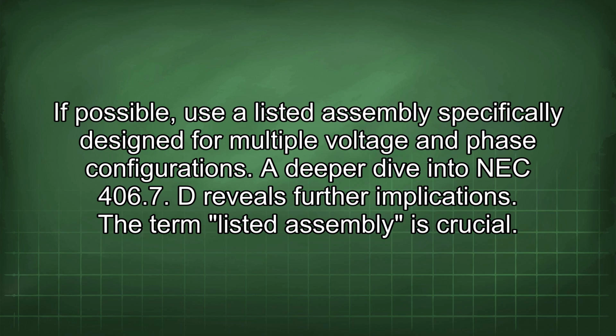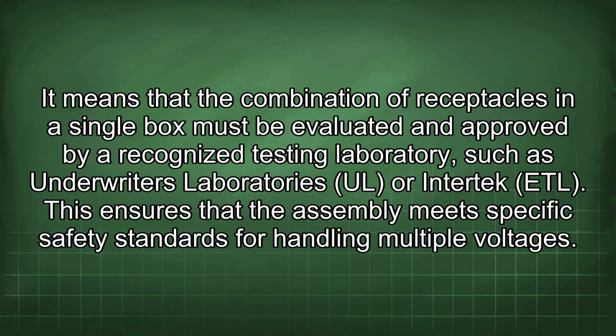A deeper dive into NEC 406.7(D) reveals further implications. The term listed assembly is crucial. It means that the combination of receptacles in a single box must be evaluated and approved by a recognized testing laboratory such as Underwriters Laboratories (UL) or Intertek (ETL). This ensures that the assembly meets specific safety standards for handling multiple voltages.